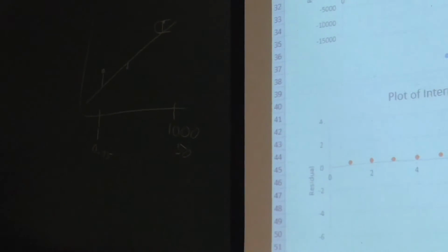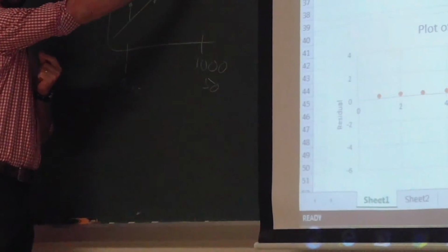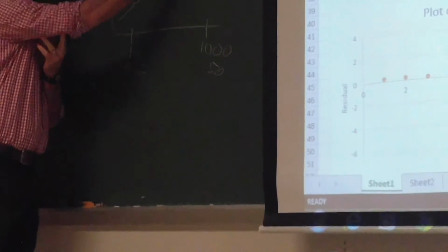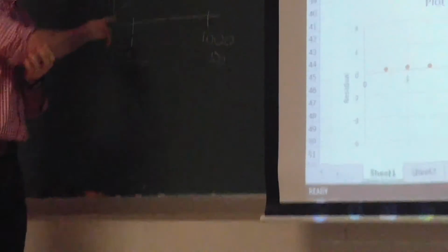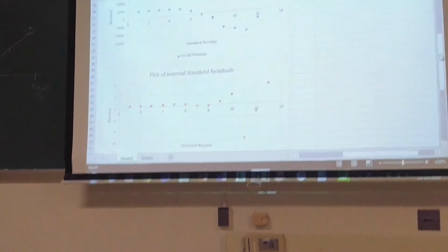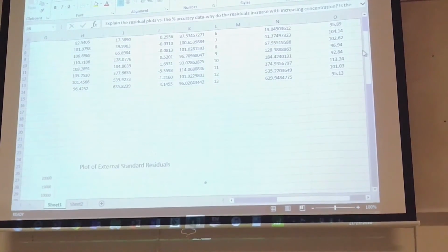and the linear least squares algorithm is trying to minimize these distances. And so what frequently happens is you do a much better job of getting through these points as compared with these points. Which is why the errors, or the percent accuracy, gets better as you go higher up in the curve, because the line more accurately represents the higher values as compared with the lower values. Okay.